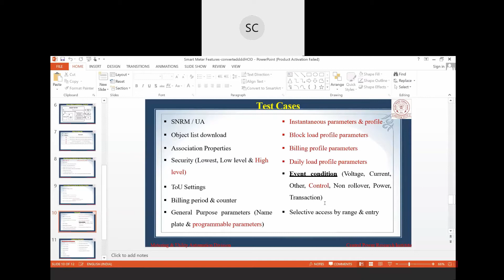Now, coming to the testing parameters, under programmable parameters, I should be able to operate the load switch. Enabled means I make the switch on. Disabled means I make it open remotely also. So enabling and disabling the load limit functions should be verified. That parameter will be verified through DLMS. Through direct contact also we will verify, as well as through communication. In both cases, it should function properly. Load limit, as I said, maximum demand load limit, will give a flag.